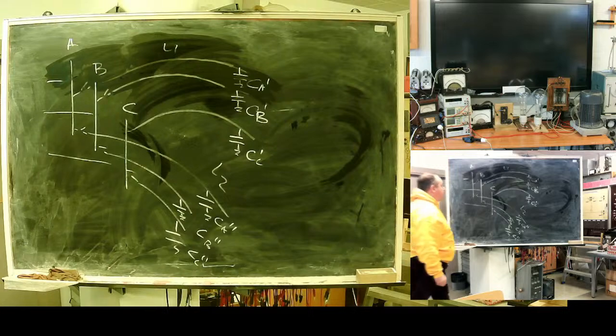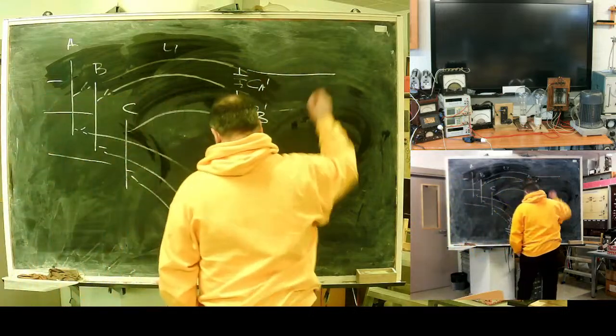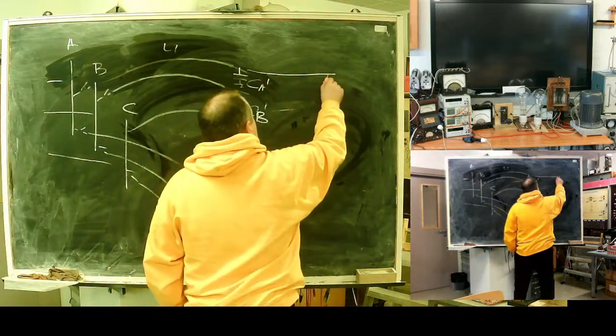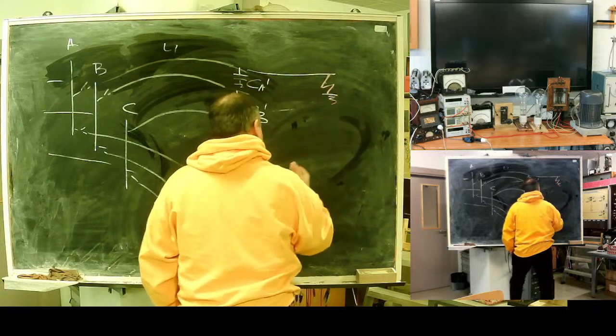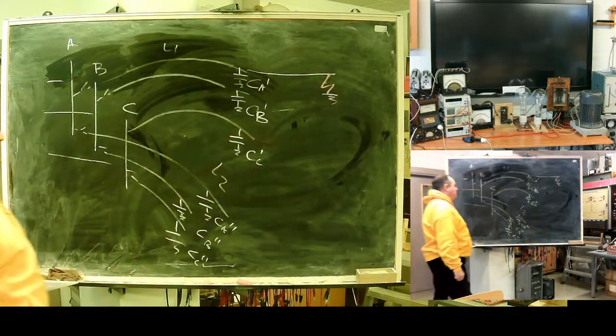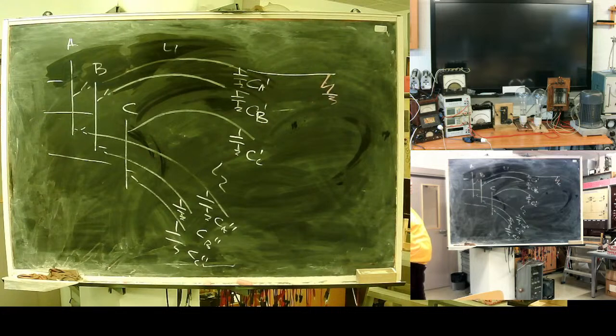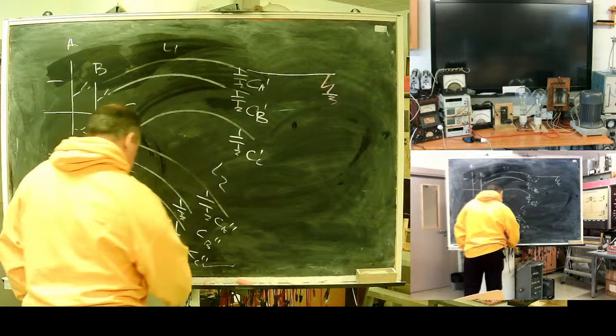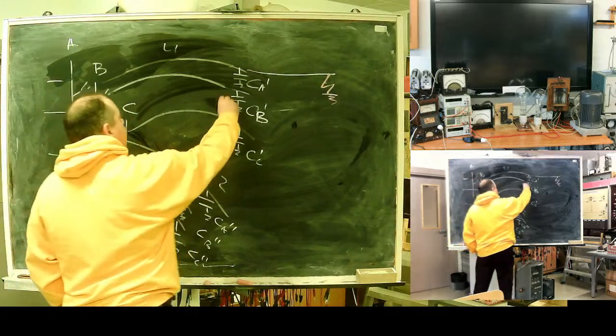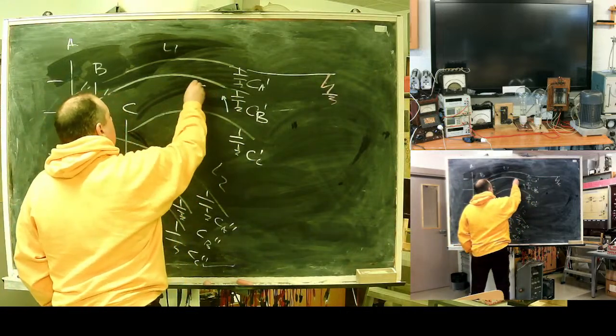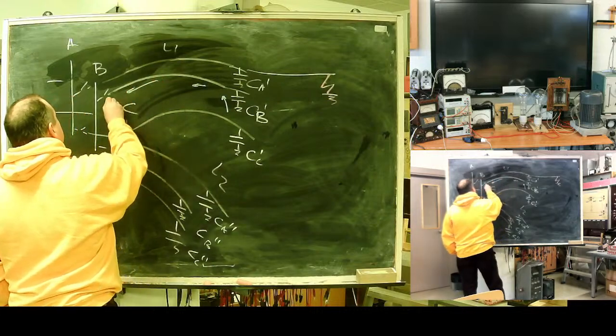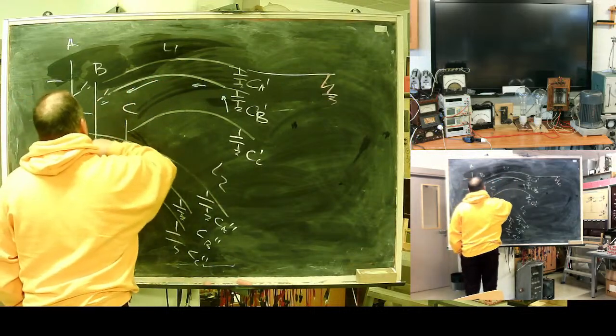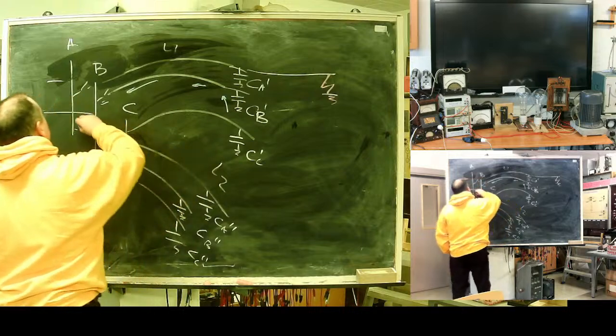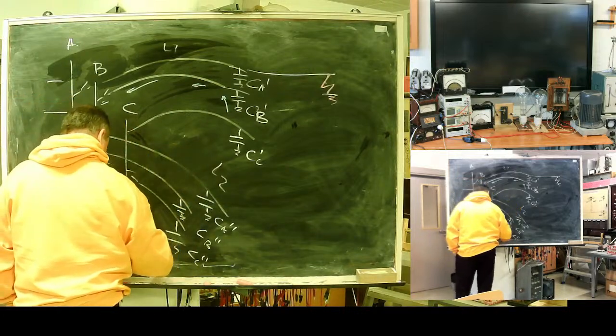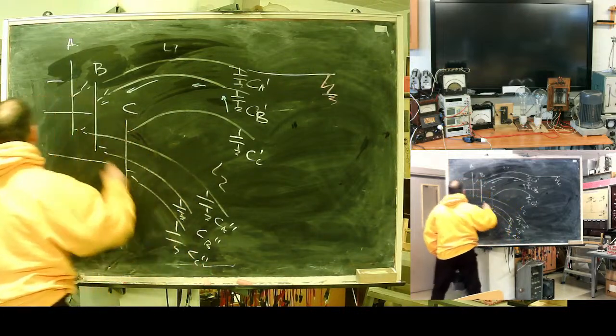This is the transformer connection, not important. What's important? Let's say I have an earth fault here at phase A. What happens? Let's try to trace currents. It will go to the transformer, and should I draw a transformer?